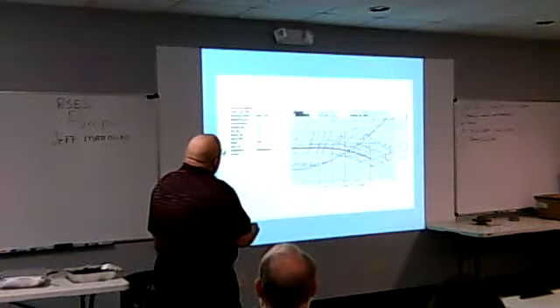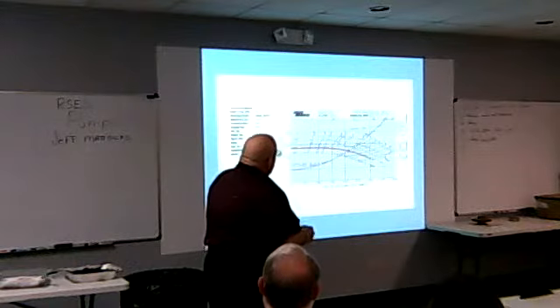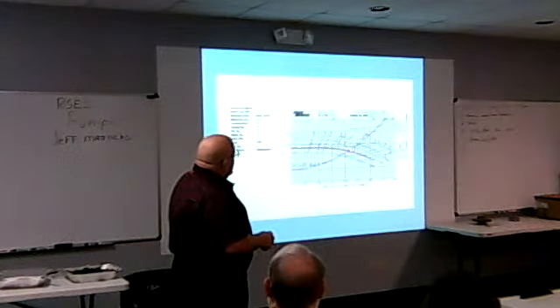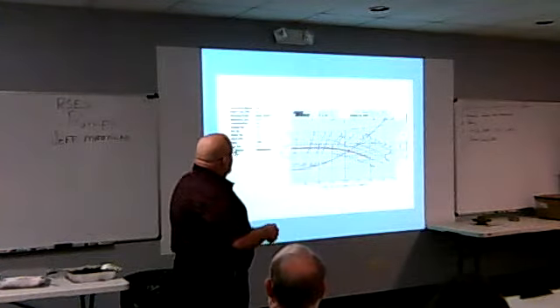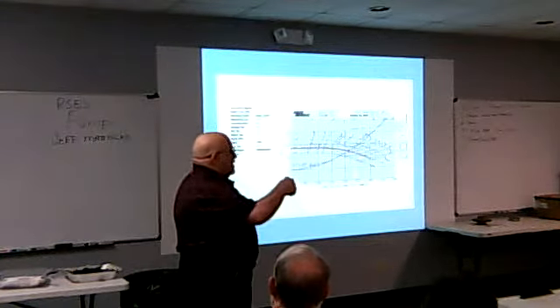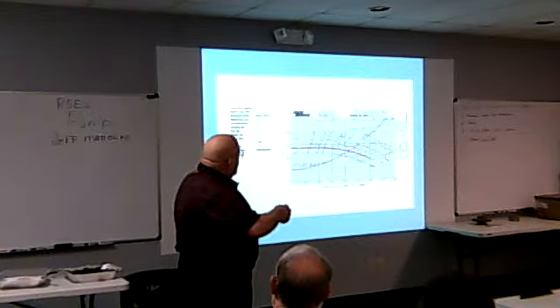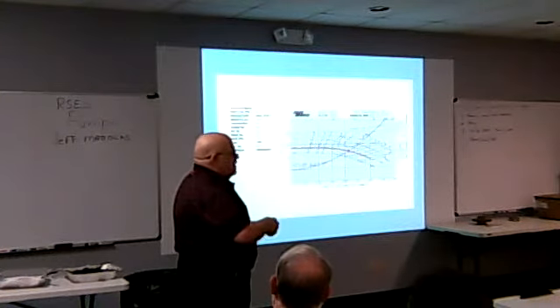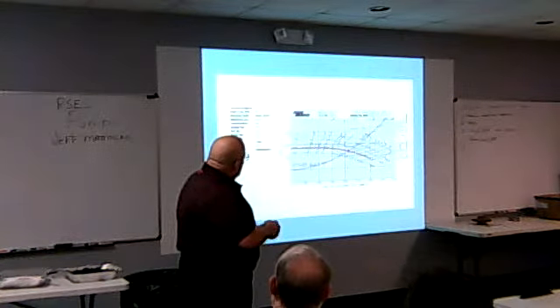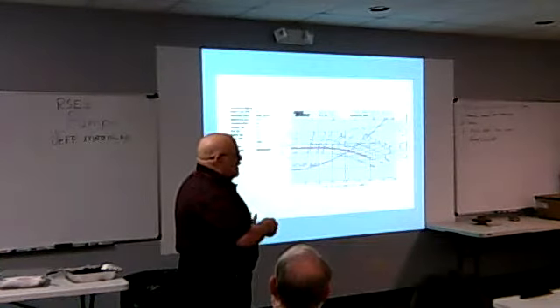All right. Oh, I meant to point out one thing here. This is the system curve right here, and I'm going to get into that in more detail. All the system curve is telling you is, from this duty point, I can calculate this. Every system has its own curve. If I throttle the balance valve, I change the curve. The pump has to operate on the curve. If this point is true, this is exactly where my pump will flow at every GPM. So if right here I'm at 215 at 70, and I come to 150, it's got to be on the curve. It has to go there. And we'll get into that in a little more.